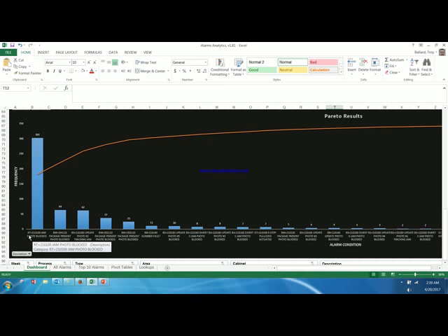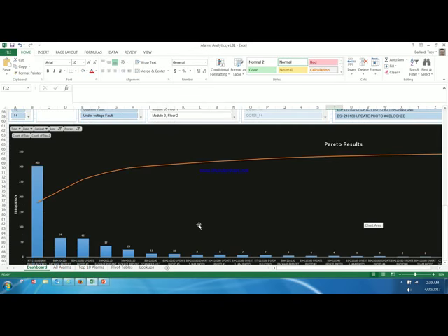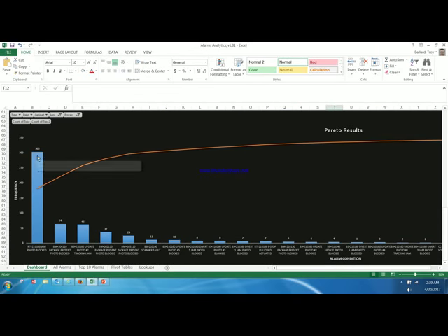It shows that we've got an RT here with a considerable amount of jams. I just picked that arbitrarily, by the way. Wow, holy smokes, this thing has got 303 jams in a period of time, which is almost 5 times what this conveyor does here. That's a potential problem.